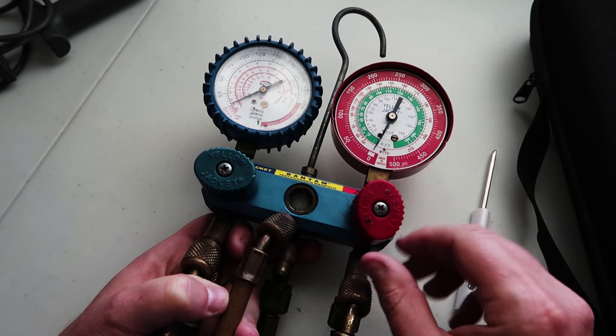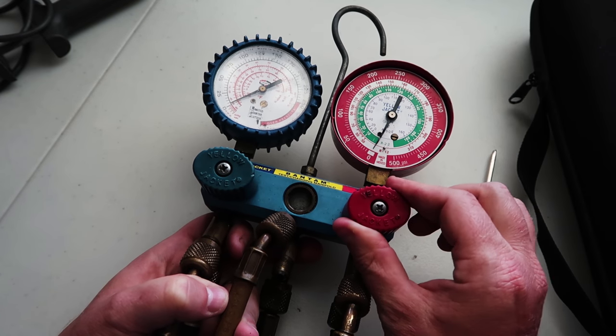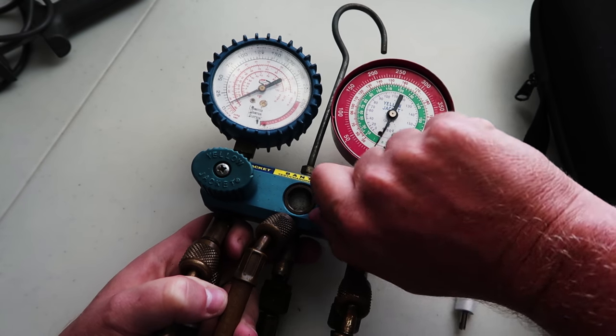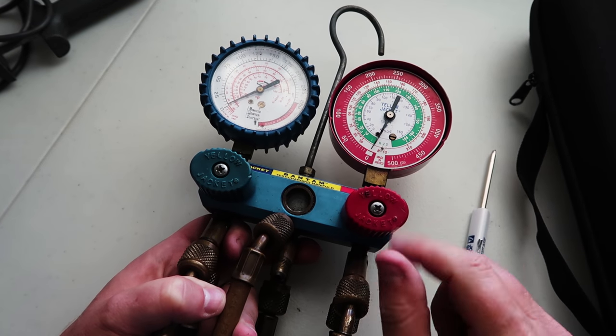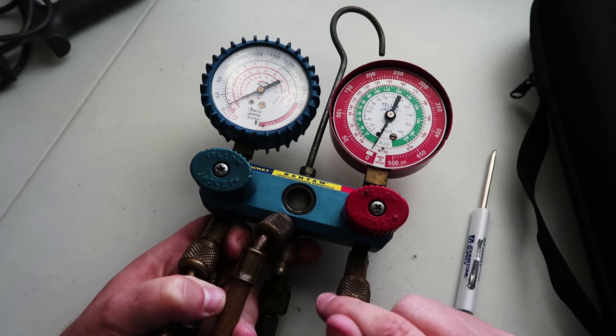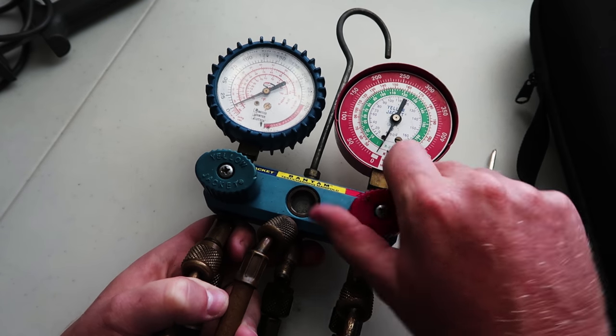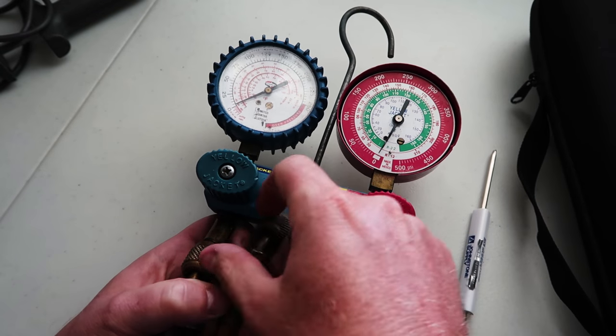Finally, what I want to say is don't over tighten these knobs. So when I turn this valve shut, I'm only finger tightening. That's tight enough. I don't need to put a wrench on it. I don't need to crank it down. If you do that, you're going to run the chance of damaging your seals inside of the valve, and then they're going to tend to leak. So whenever you're opening and closing, you're just doing it with finger tight.